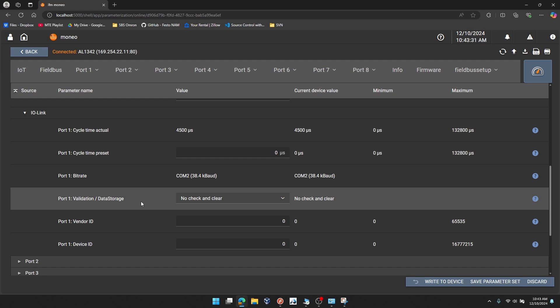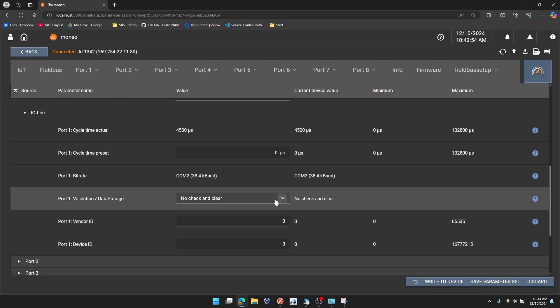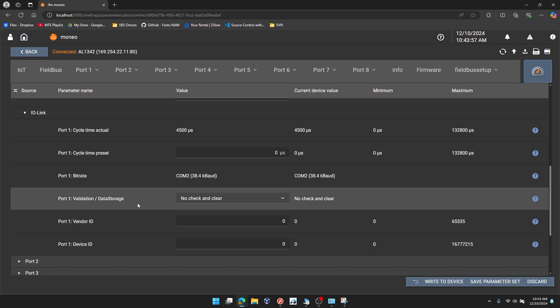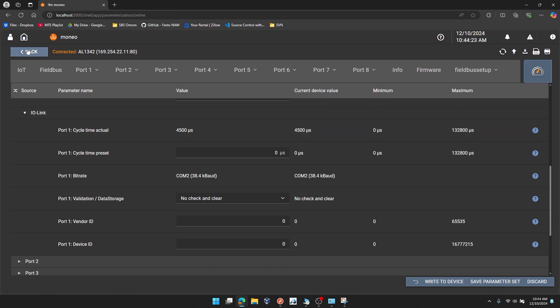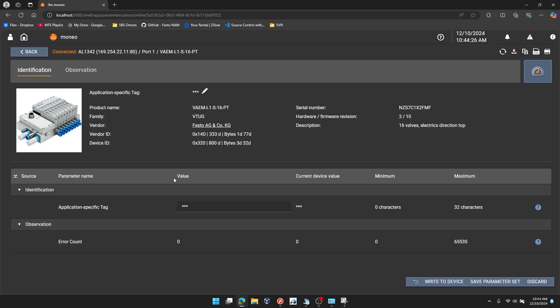And these last three settings are what we're really concerned with here. This is the ability to check if the connected device is a Festo device. And if that Festo device is exactly the same VTUG. So the first parameter we're concerned with is port 1 validation and data storage. You can see it's defaulted here to no check and clear. So any IO-Link device can really connect to that port at this point in time. I'm going to click the down carrot. And I'm going to select type compatible v1.1 device. So how do I know that the IO-Link valve terminal is a 1.1 device? Because it's a connected device, I can actually go back to my device noted here. And you see a few things that are important to note. The vendor ID is decimal 333 and the device ID is 800. We'll come back to that in a moment.